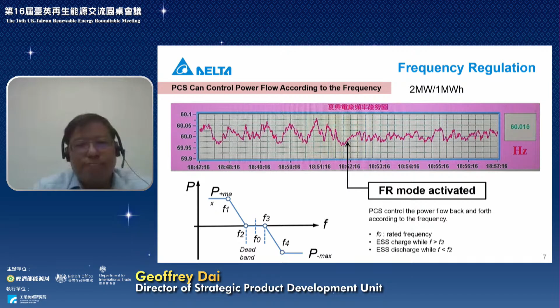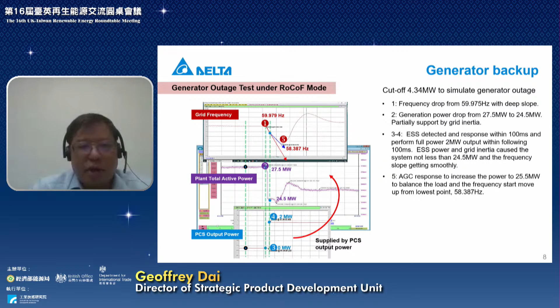This made the frequency more stable. There was one case where they tried to drop 4.3 megawatts of power and the frequency dropped very quickly, but our energy storage responded in 100 milliseconds, reaching full power and making the frequency drop slope smoother, so the grid did not black out.